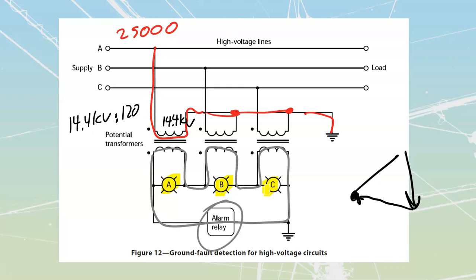As soon as I ground down one of my lines, that grounding short out to this grounded point, this grounded Y. Remember, instead of lights across the center, now we have PTs across the center, so instead of a light going out, a PT is going to go out instead. So if we lose our C type PT, we end up with a voltage differential going across from here to here.